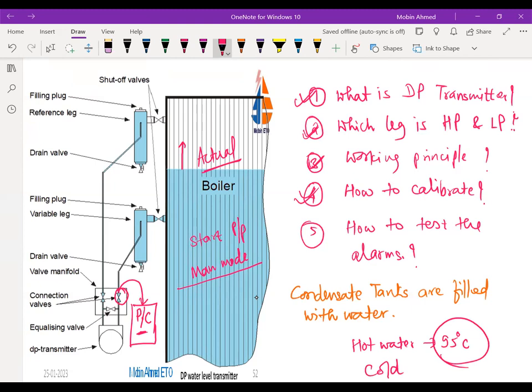Are you getting me? So this becomes cold water, although it is 95 degrees centigrade, because the water temperature here is quite high. It is 150 degrees centigrade. So you need to slowly fill this water, so there will be no thermal stresses. And once you reach the high level, this alarm is supposed to come, and again, if you continue, then the high trip will also be there. Hope it is clear.